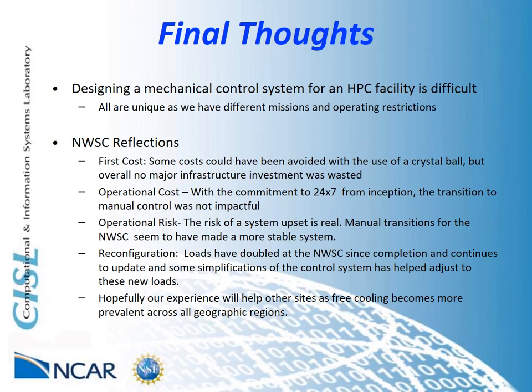The team's operational risk reflections are that the system upset risk is real, and that the NWSC's change to manual transitions is felt to have provided a more stable system overall, especially as the IT loads change. Finally, reconfiguration is constant. The NCAR IT loads have doubled since the initial startup of the site, and it continues to go through changes and upgrades across the full IT hardware kit. Simplifying operations and including a few manual transitions has supported these reconfigurations well.